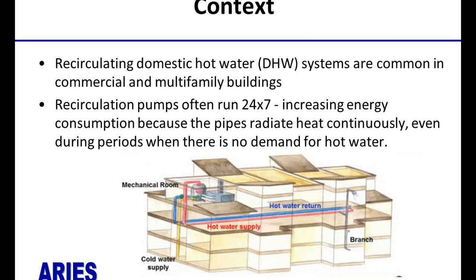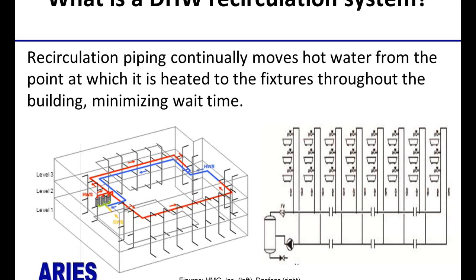To provide some context, the central recirculating domestic water systems are common in multifamily buildings. Often the recirculating pumps run 24 hours a day, and many times without any sort of control. And that increases energy consumption in two ways. The primary way is that hot water recirculating through those lines loses heat to the surrounding environment through radiation. And minor energy loss is also due to the pump energy, which is running continuously.